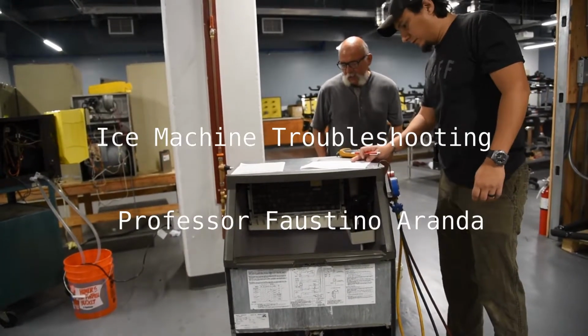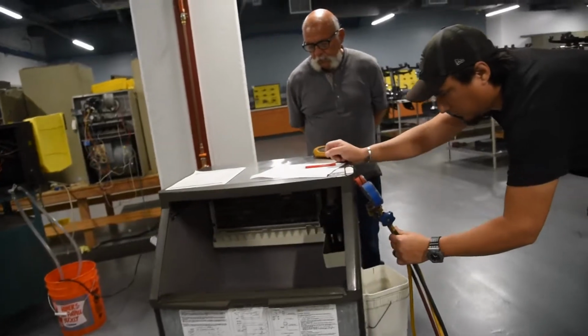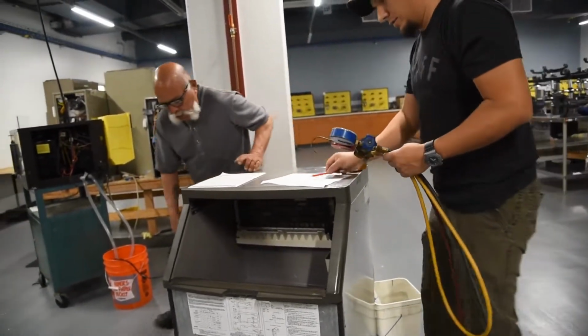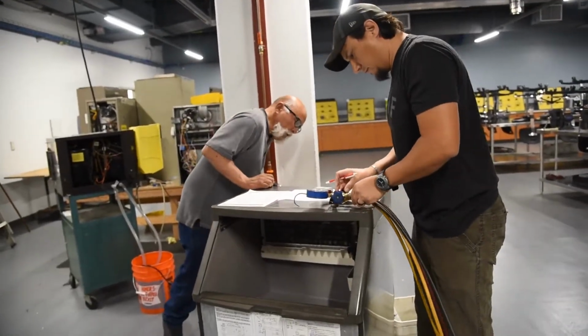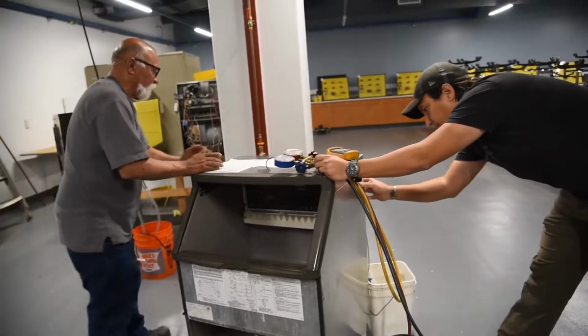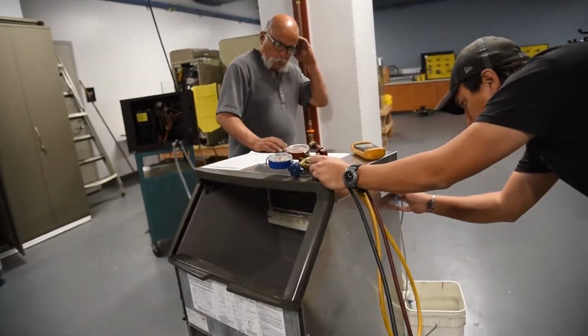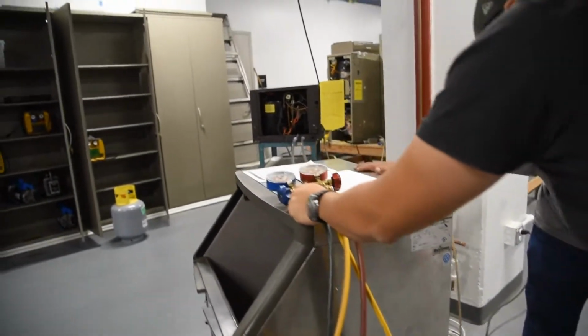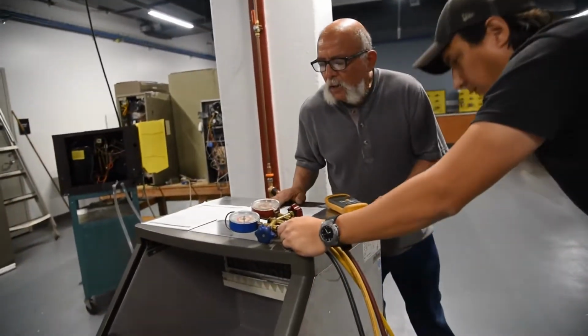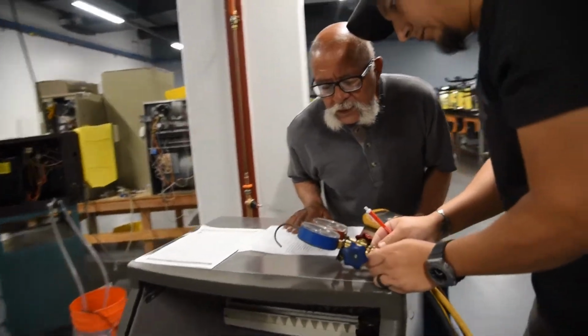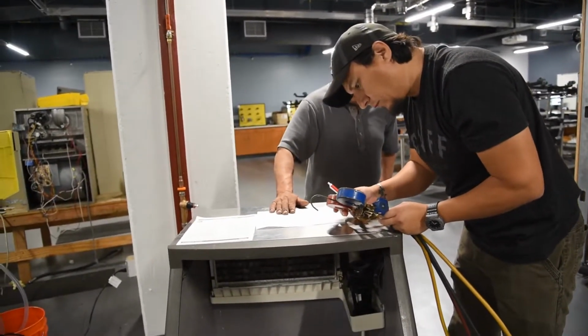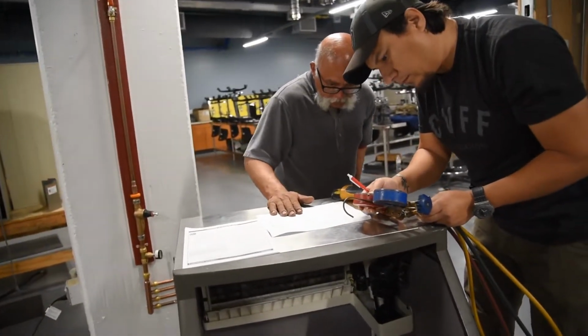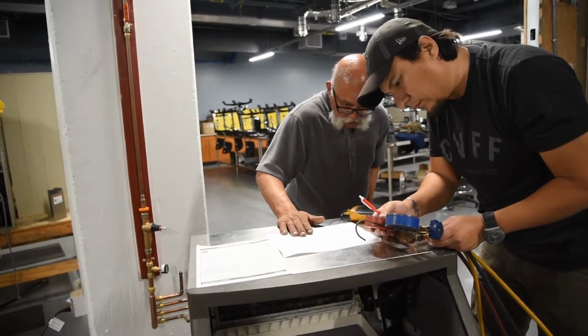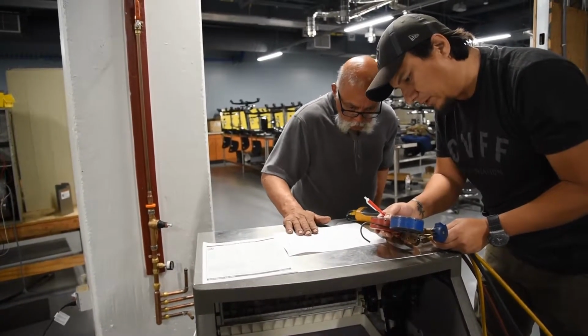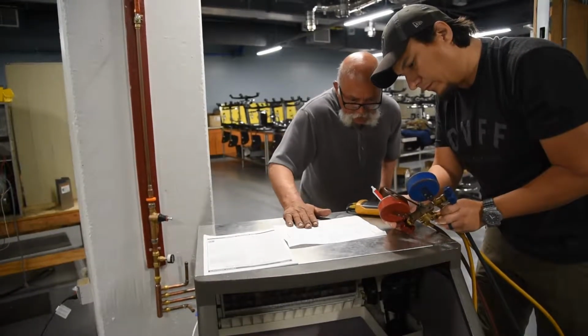The high pressure temperature is set? High pressure temperature. What is the refrigerant in this? That is tag right there. So it's 404. Okay, 404, and we have 404 on the scale. It's the orange one. Okay. Pressure is 275. Temperature is 112, something like that? We'll call it 110.